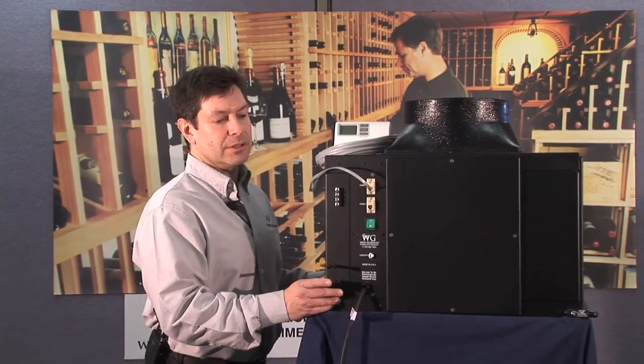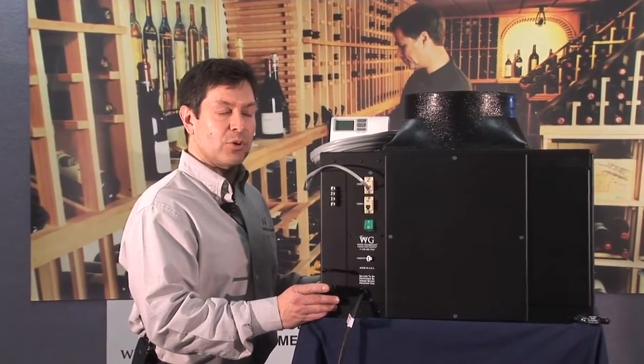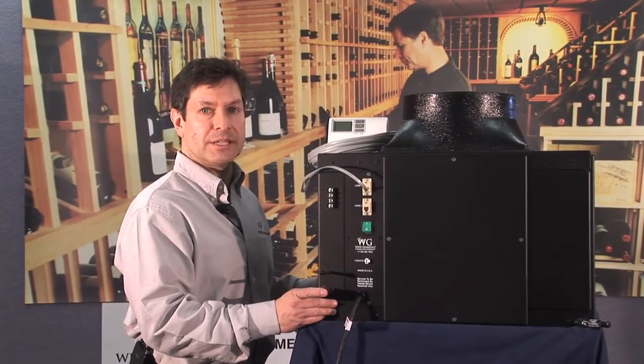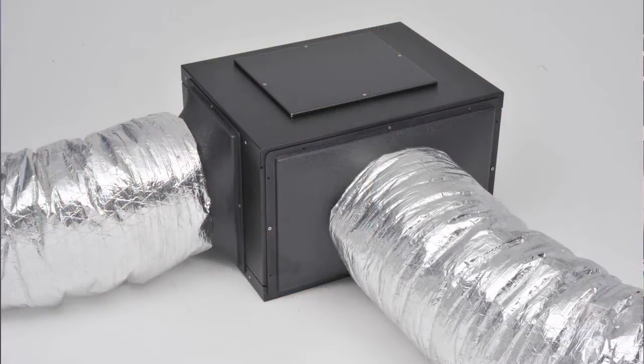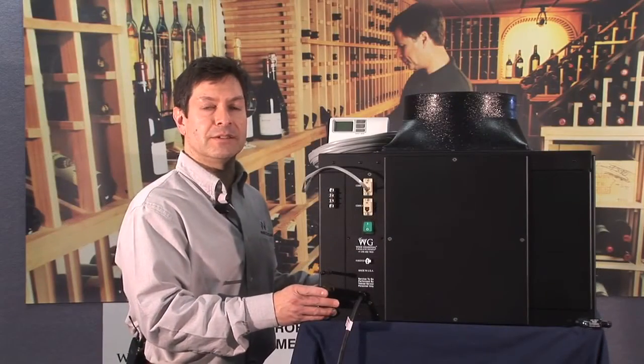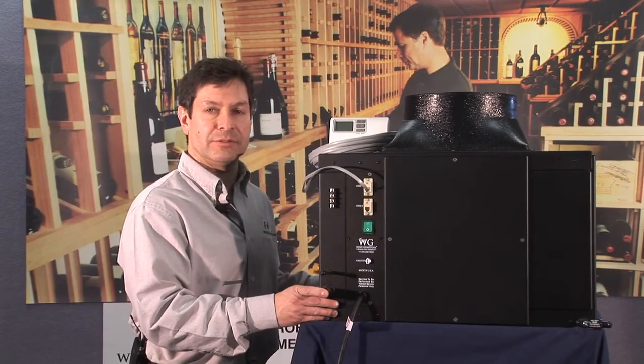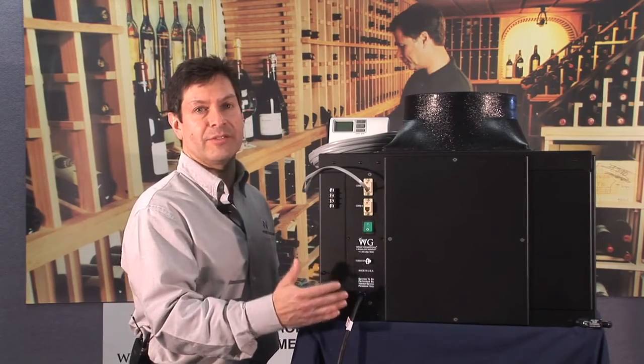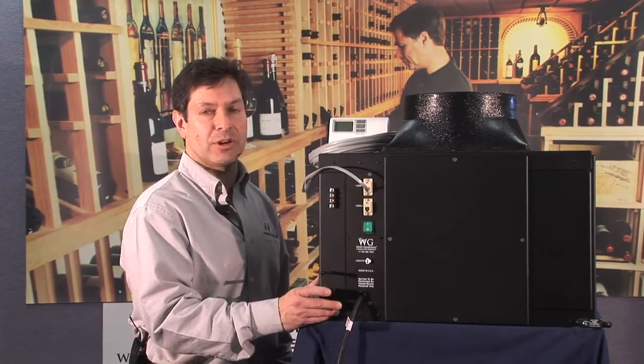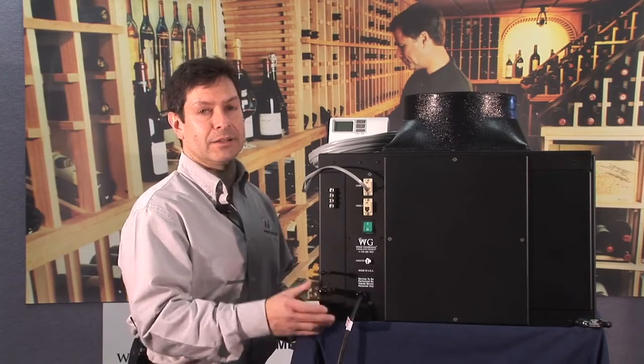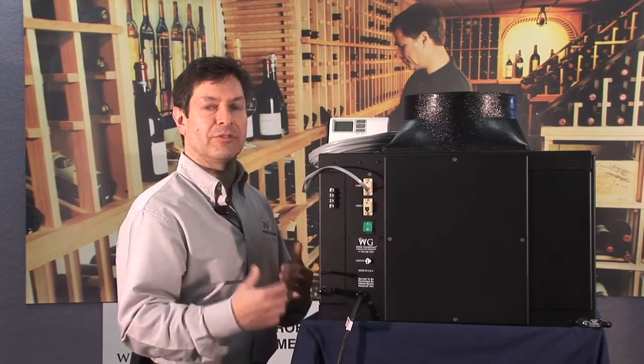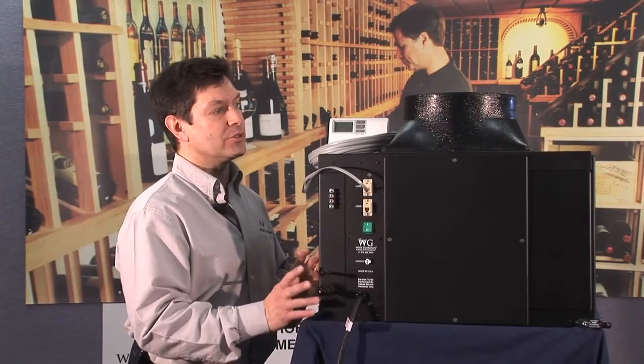On our SS025, which is our quarter ton, up to our 1 ton systems, you have the ability to connect up to 25 feet of flexible ductwork. So the system should be within 25 feet of the wine cellar itself. You can go beyond the 25 feet if we interject some rigid ductwork. Beyond that, booster fans just to keep that airflow moving. But we rate those for 25 feet.